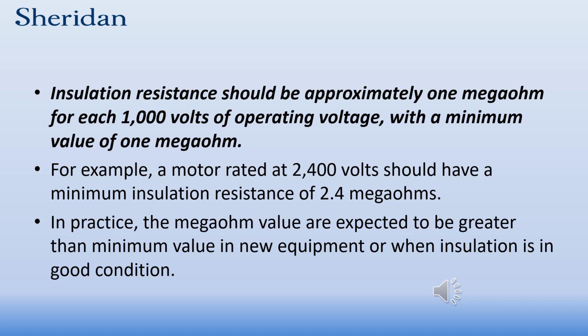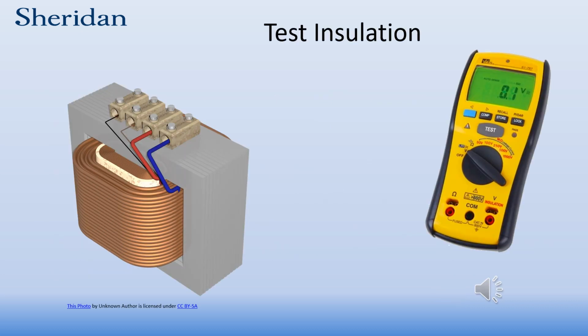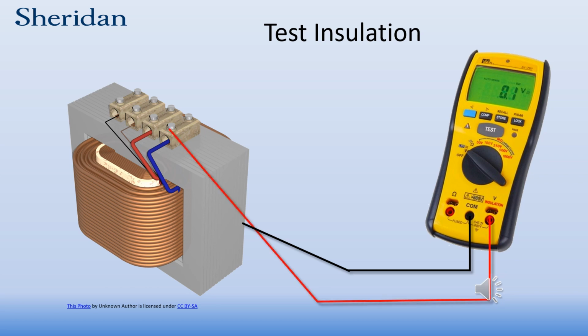My recommendation would be 10 megohms minimum for a brand new piece of equipment. So where and how do you test? First, it is always imperative to make sure you do have a good connection to any of the terminal points or to the chassis of the transformer. Once you've established that, you make a connection to the chassis and one to any one of the terminals and take the test from there.